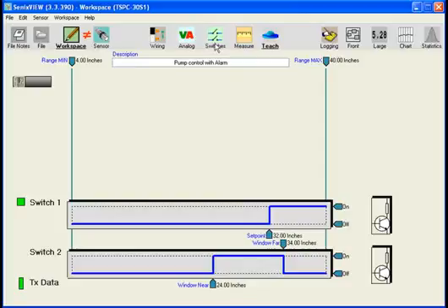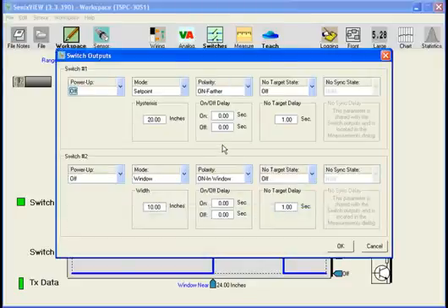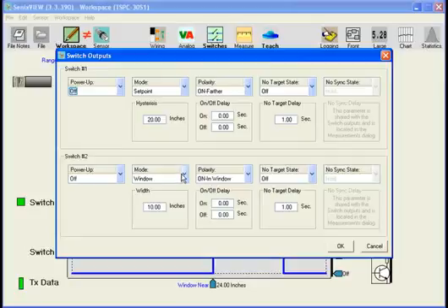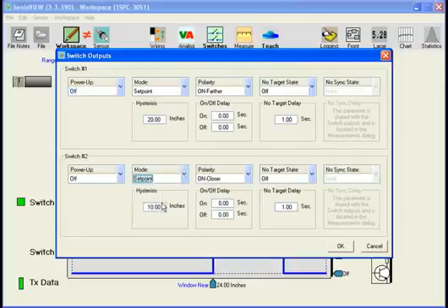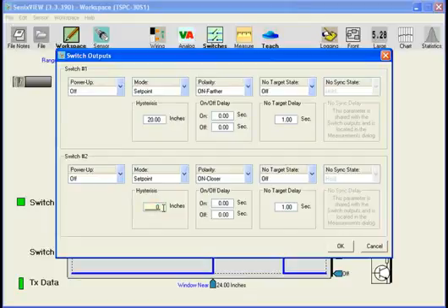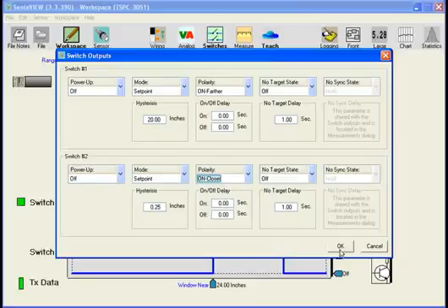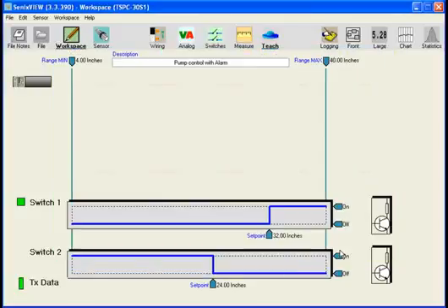And we'll go to the switch output window. And in this case, you remember we had switch two set in a window mode. So we're going to go back and put that in set point. And now we want a small hysteresis, not a big window. So we can okay out of that. We'll leave the rest of it the same.